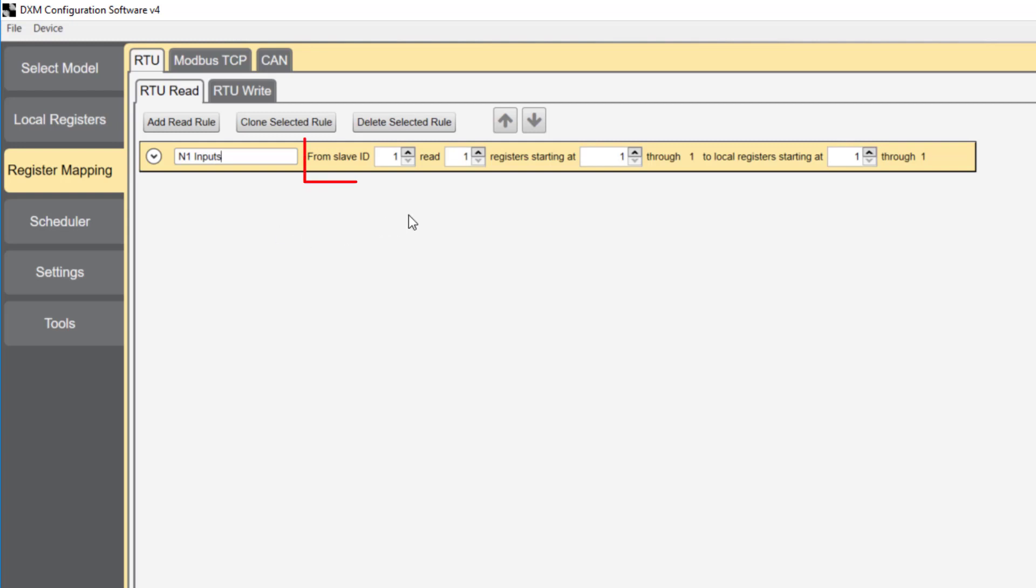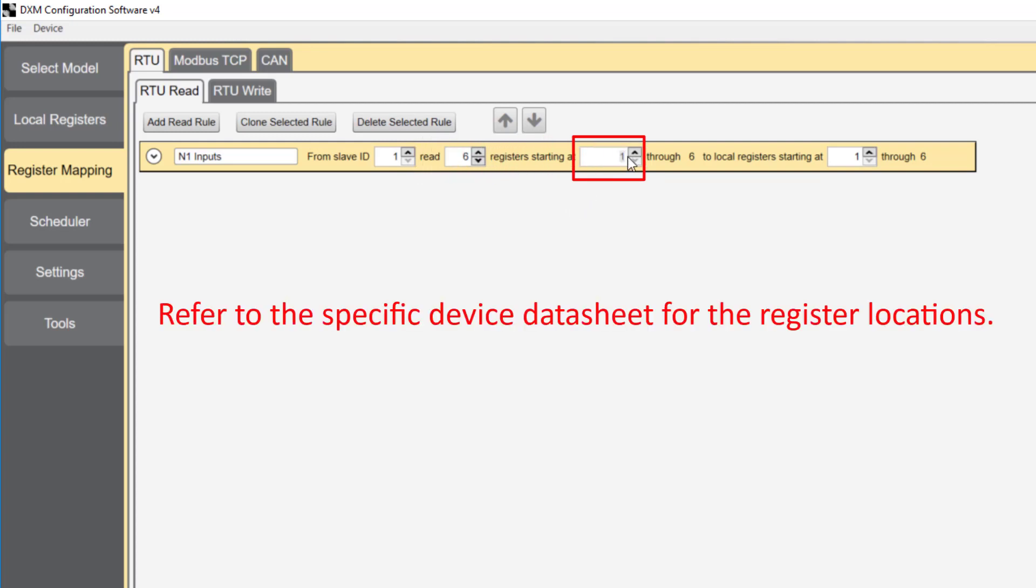From slave ID 1, which is the radio board, we're going to read the first six registers from node 1, starting at register 1, which is the first input of node 1. We're going to store that data in the first six registers of the local register.